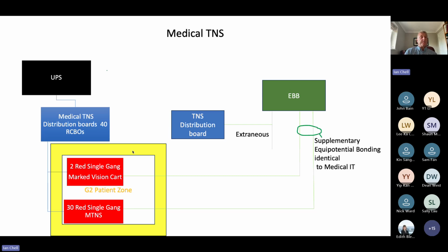And then you have your normal TNS distribution board for sockets outside of the patient zone, and they would be white, whereas the medical TNS are red. This is because of the advice that somebody suggested, because currently sockets that are supplied by the UPS have red switches on them. So this just takes that further. Obviously, I'm not a standards guy. I'm not employed by anybody anymore, but these are strong suggestions that need to be considered.